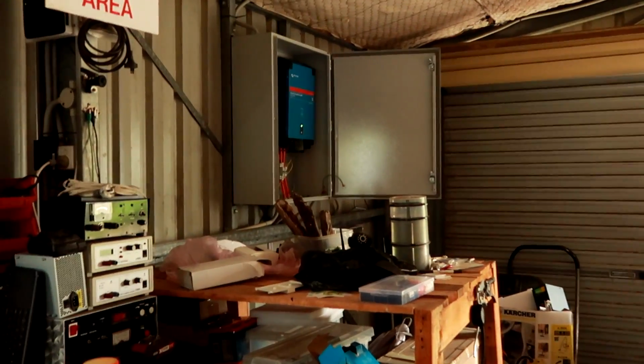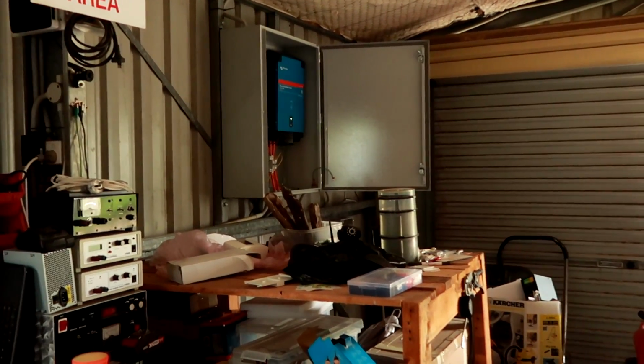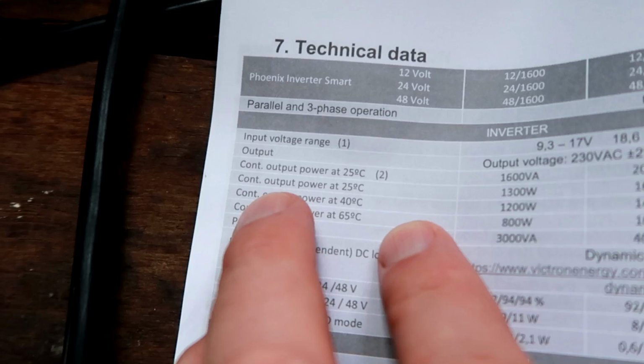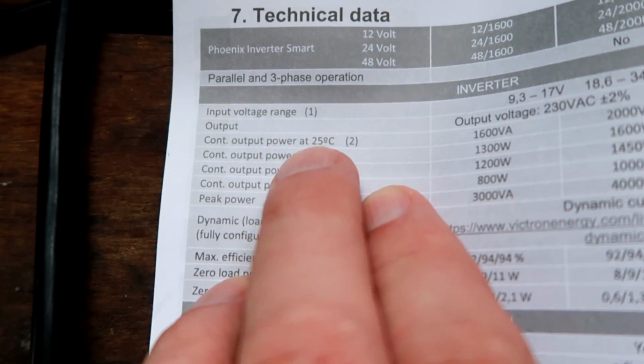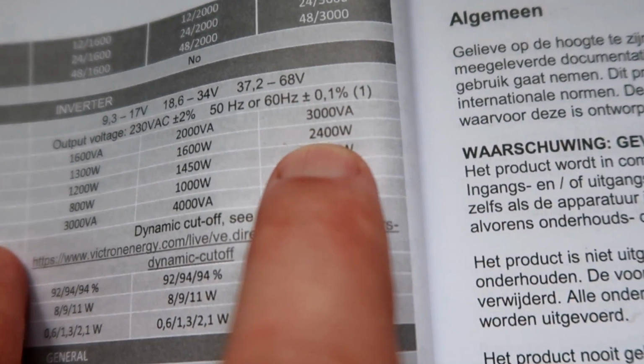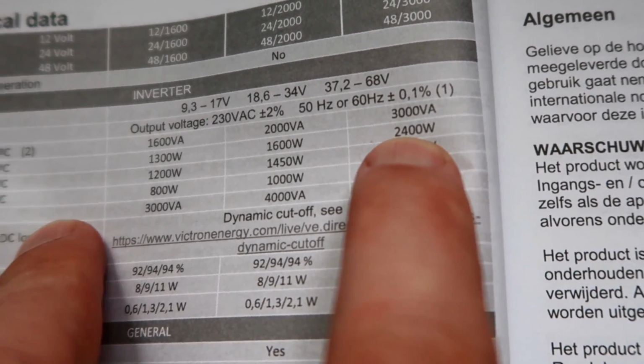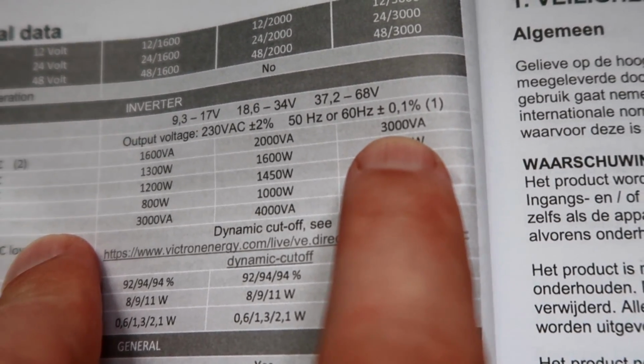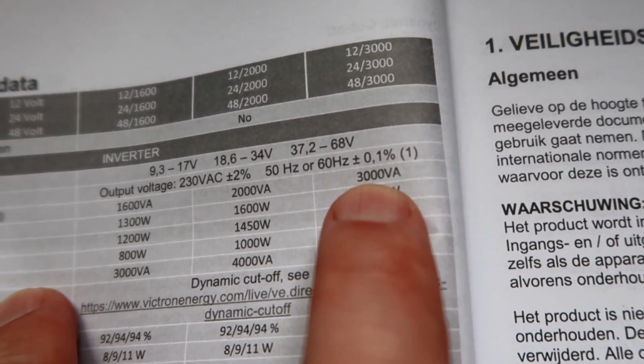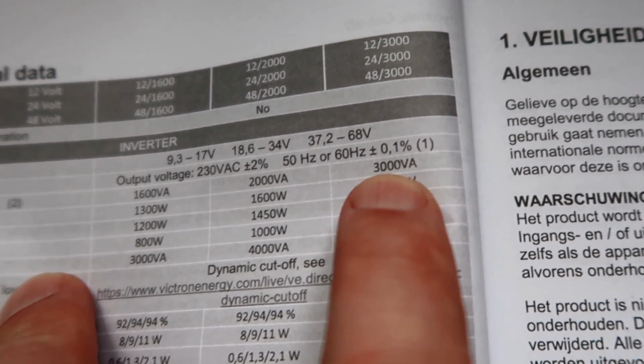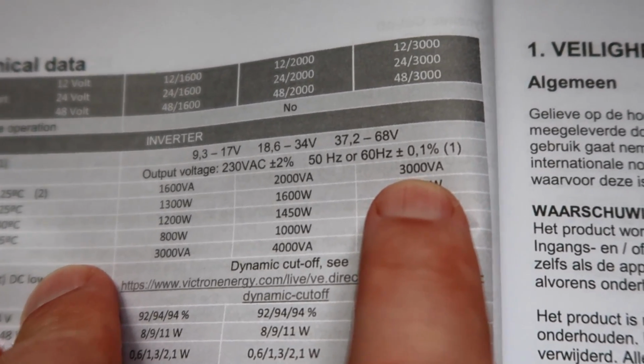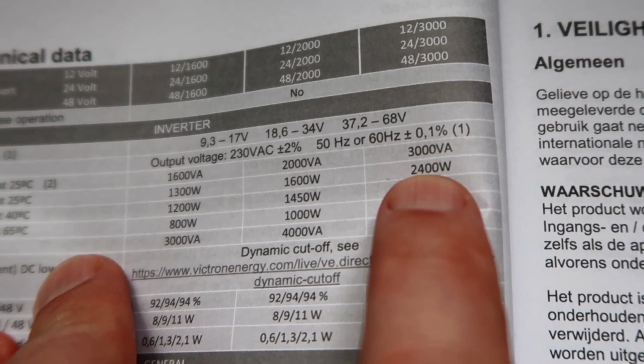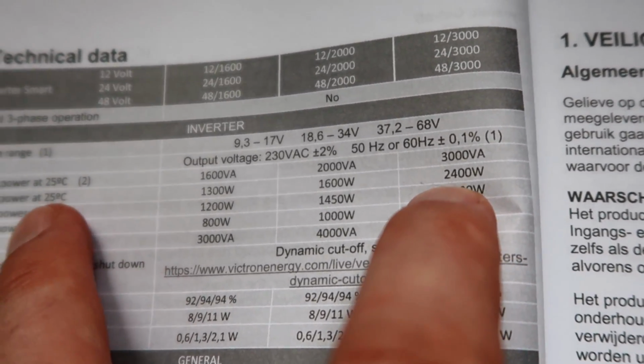I'm really not so concerned about the inverter stuff and the heat it produces. It was an extreme hot day today, so that was just me testing it out. If you look in the manual, the continuous output is explained at 25, 40, and 65 degrees. On the right hand side, it's 2.4 kilowatts at 25 degrees, so the 3 kilowatts you will only get with cold climates. I will probably get that in wintertime when it's cold here, but in summertime now it's 2.4 or even only 2.2 at 40 degrees.